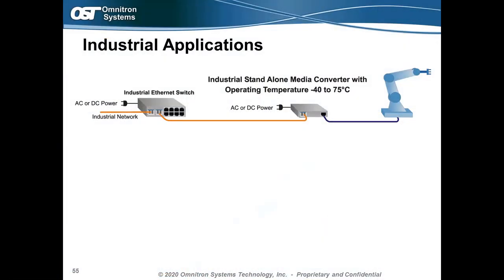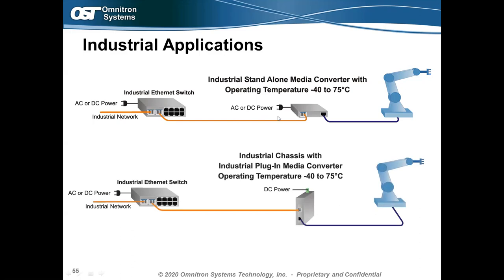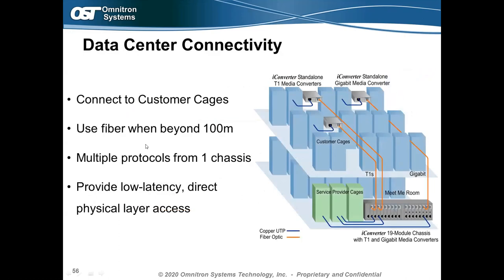In industrial applications, Omnitron's industrial media converters run fiber from an industrial Ethernet switch to the factory floor and convert to copper. The key requirement is a media converter supporting an industrial temperature range — negative 40 to 75°C (up to 167°F) — powered by AC or DC. Omnitron also offers industrial chassis where industrial-rated media converter cards can be plugged in, supporting that negative 40 to 75°C range, with DC-powered and flexible architecture for swapping different converters by application.